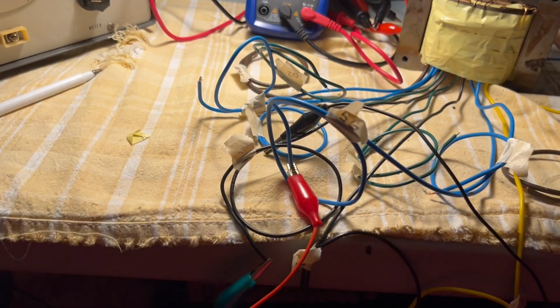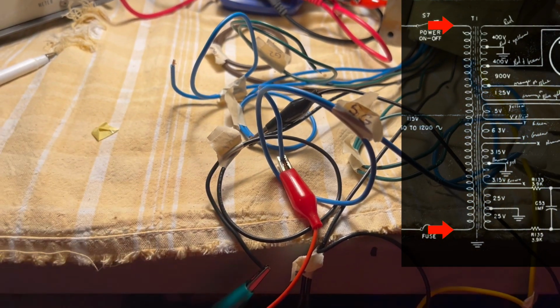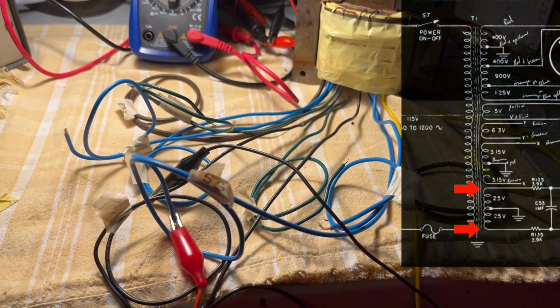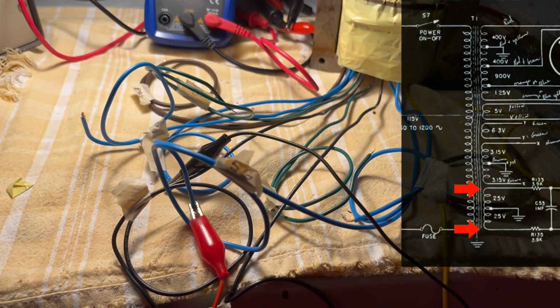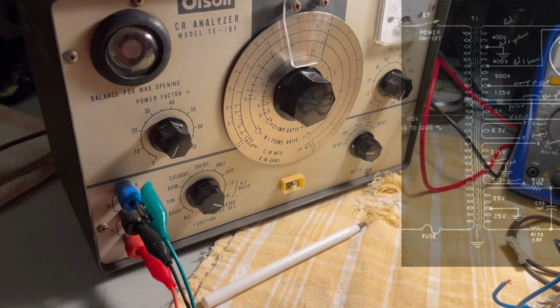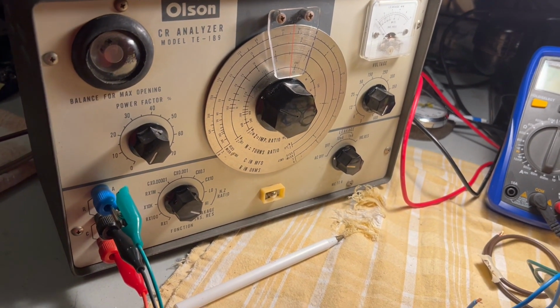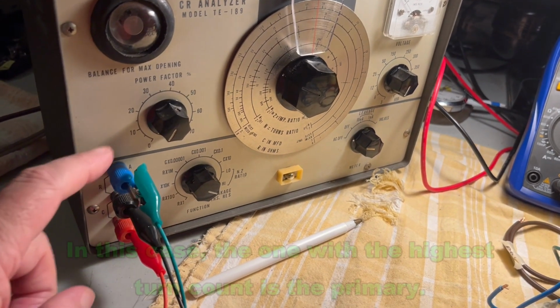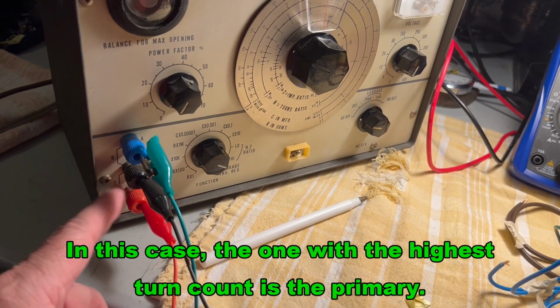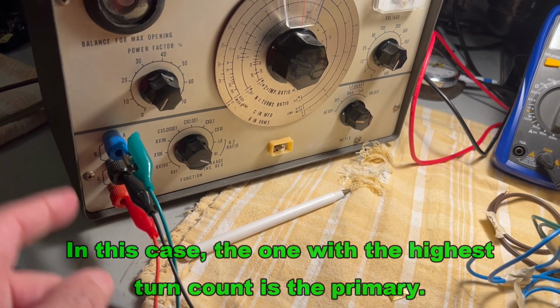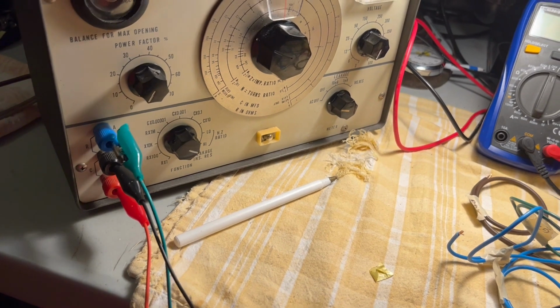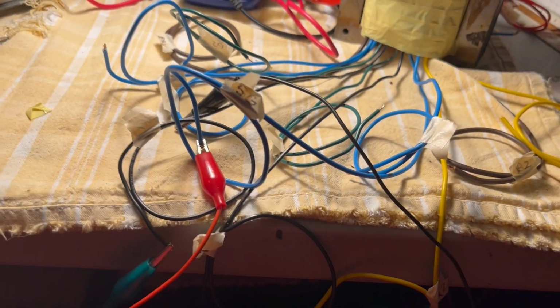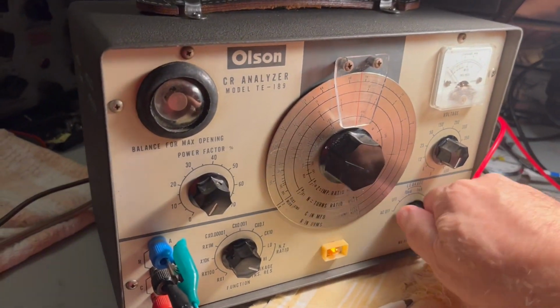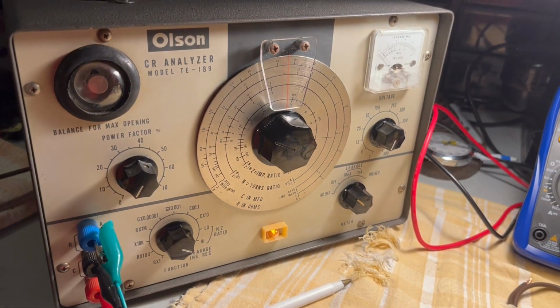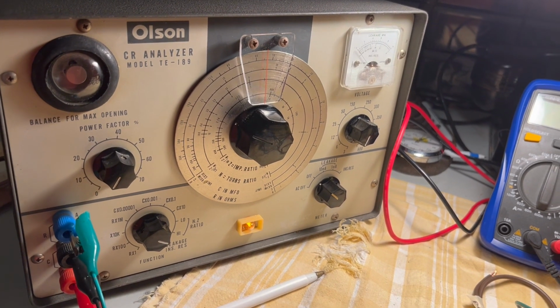What I've got now is I've got it attached on one side to the primary and on the other side to one of the secondaries. It's the one that's 25 volts from the center tap and 50 volts end to end. Okay. The way this sets up, I've talked about it before. The one with the highest turn count would be the one that you put on the top here, and the one with the lowest expected turn count would be on the bottom. So you put the positives on these colored terminals, and then you tie the negative sides of the two coils together on this black lead in the middle. So that's how you set it up. And I'm just going to turn this on, give it a chance to warm up. Just want to demonstrate how it's done, and then I'll go through and do it for all of the rest.